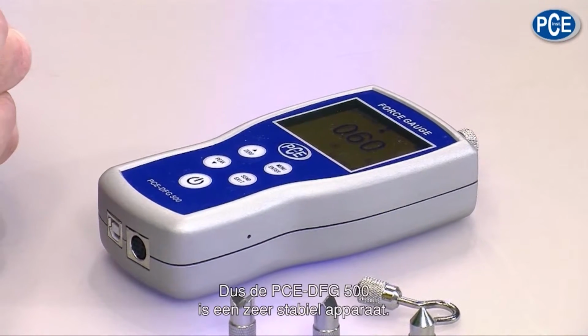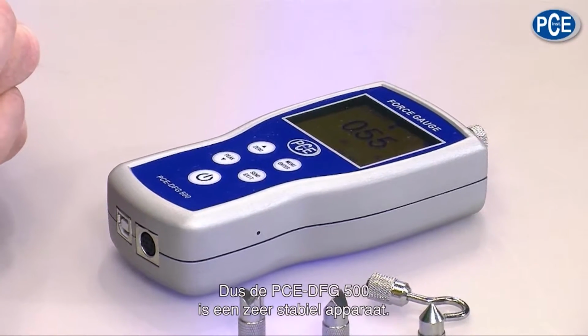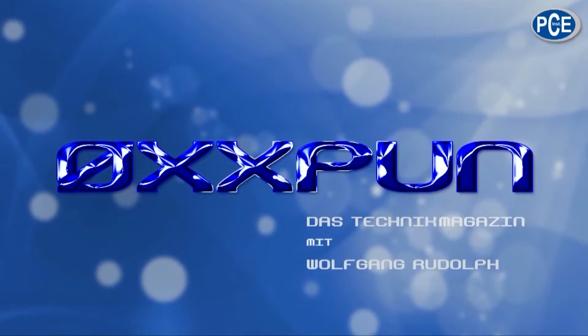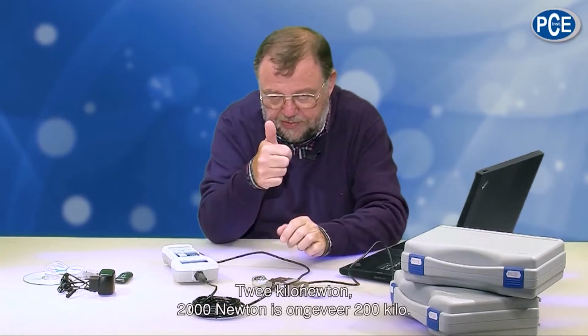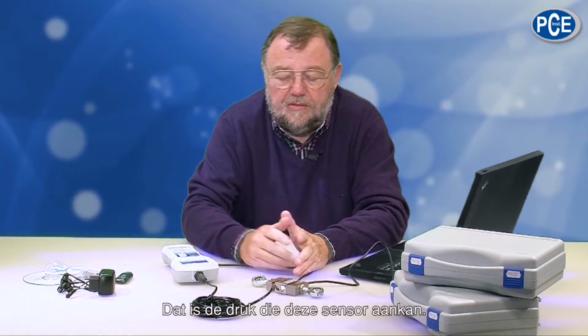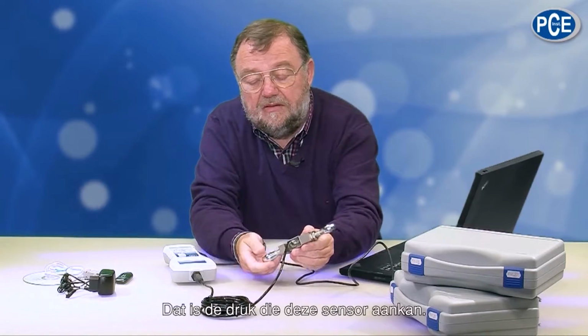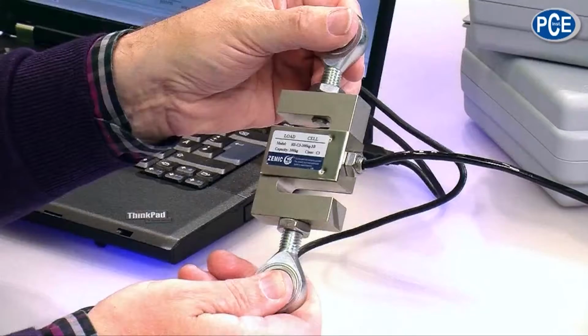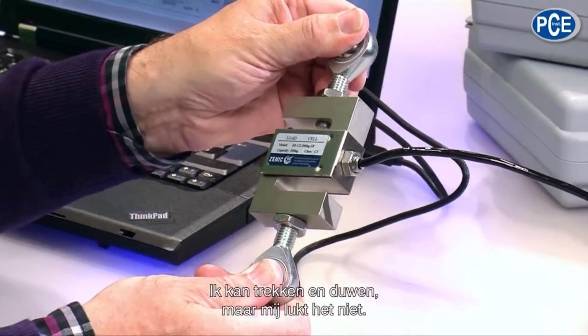So the PCE DFG 500, a very stable device with up to 1,000 measuring values, can save and also 10 hours of working time with the battery. 2 kilonewtons, 2,000 newtons, is so about 200 kilos. That is what this sensor can manage. I can pull and push, but of course I can't manage it.